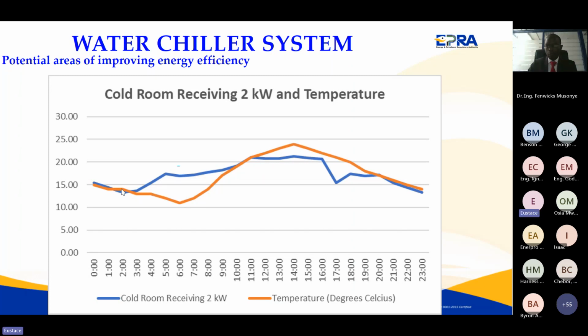Now you can see between 3 and around 6 in the morning, the temperatures are reducing, but the power consumption went up. So you need to identify what is happening in this area and give an explanation, because it can be recurring throughout. Probably it was poor setting of the control systems. And that might have been a major source of energy consumption, because these are many hours, 3 to 6.